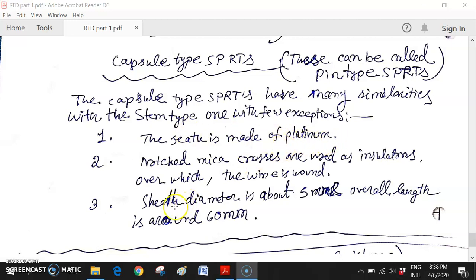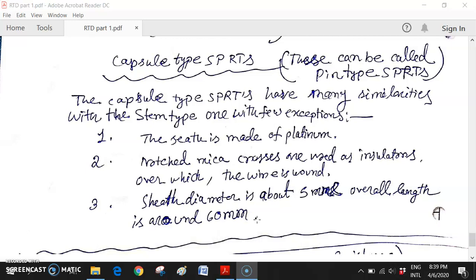Here, directly a platinum sheath is used. The sheath diameter is about 5 millimeter and overall length is 60 millimeter only. For stem type, the sheath diameter was 0.7 centimeter and length was 400 to 800 millimeter. Compared to this, it is only 60 millimeter - very small - and diameter compared to 0.7 centimeter in stem type, it is only 5 millimeter. That's why the name is capsule type SPRT.